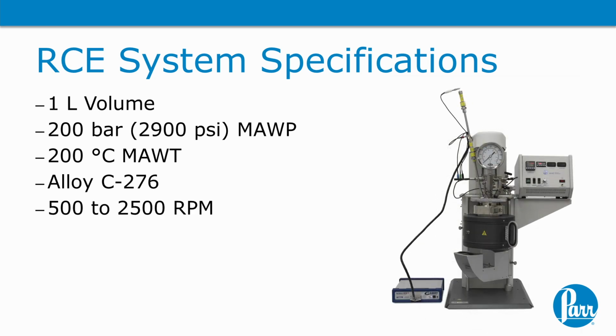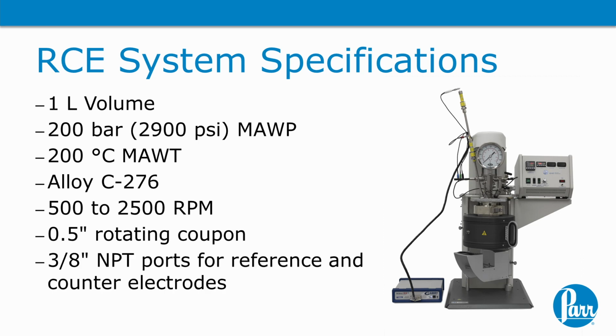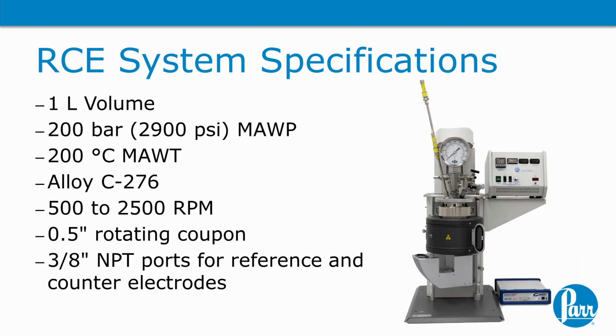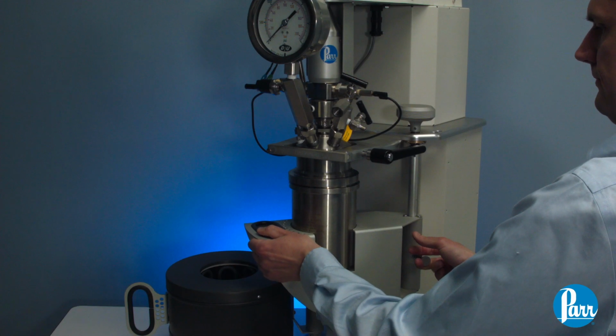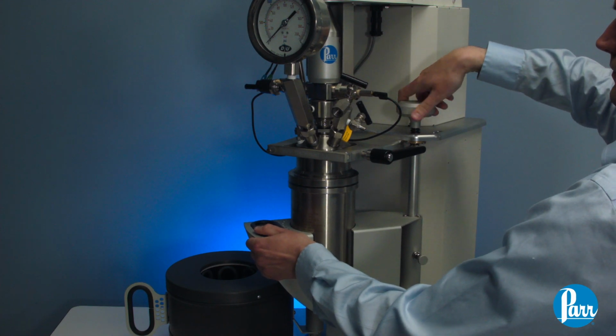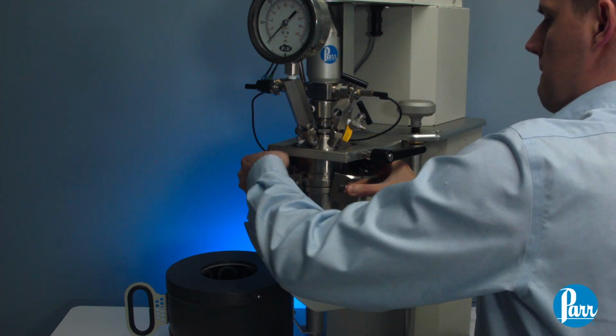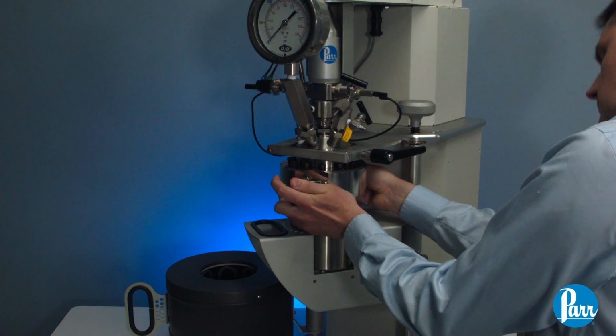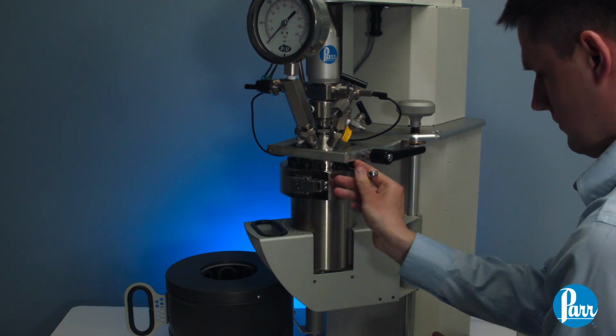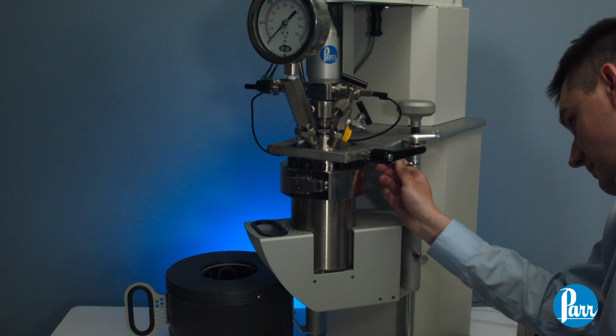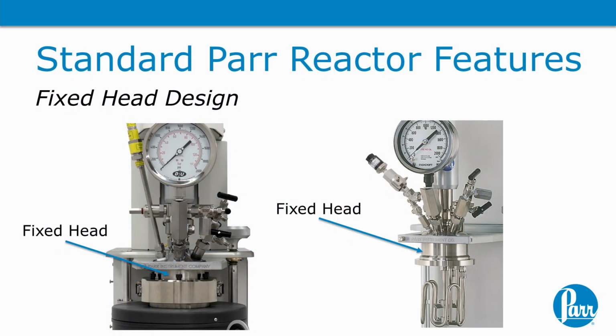Testing can be performed at rotational speeds ranging from 500 to 2500 RPM. The rotating cylinder coupon has a 1/2 inch OD. There are two 3/8 inch NPT ports on the head for mounting the required reference and counter electrodes needed for the corrosion testing. This RCE is based on a standard Parr reactor and has standard features familiar to Parr reactor users. This is a fixed head system, which means the head is conveniently fixed to the support plate on the stand with a machined flange. The head can be removed from the stand when necessary for servicing or cleaning.